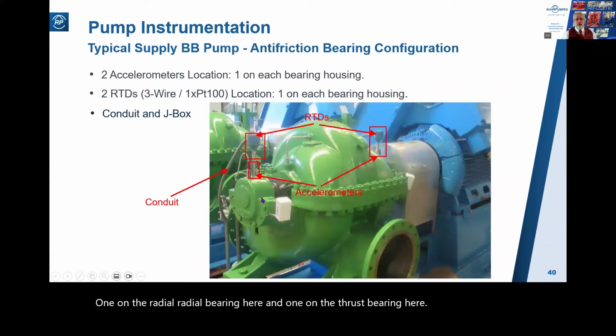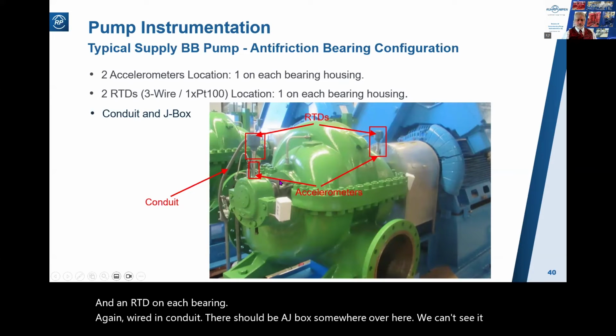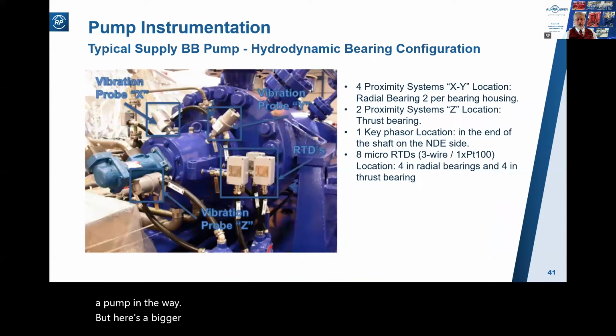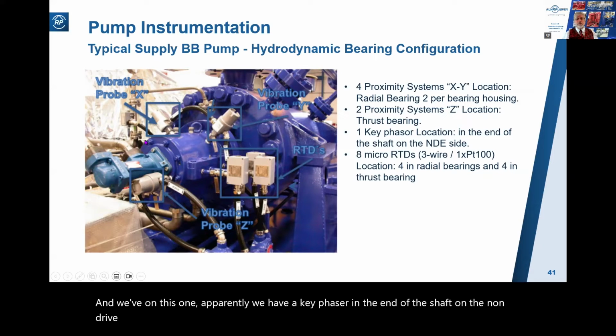Here's a typical between bearings pump with ball type bearings. So we see an accelerometer on each bearing and an RTD on each bearing. Again, wired in conduit. There should be a J box somewhere over here. We can't see it. There's a pump in the way. And here's a bigger pump with hydrodynamic bearings. So we have an X probe, a Y probe, a Z probe. We have some RTDs, and on this one, apparently we have a key phaser in the end of the shaft on the non-drive end, which is unusual. It's more commonly on the drive end. We'll see that in a next slide.